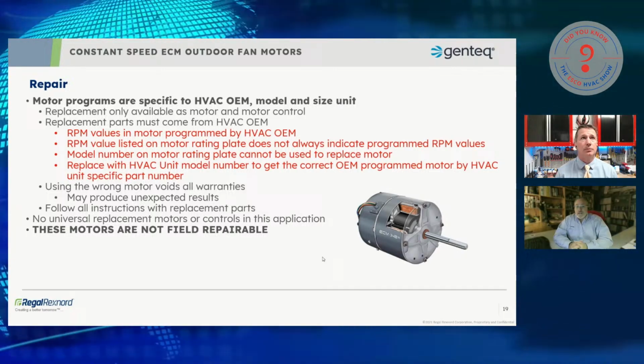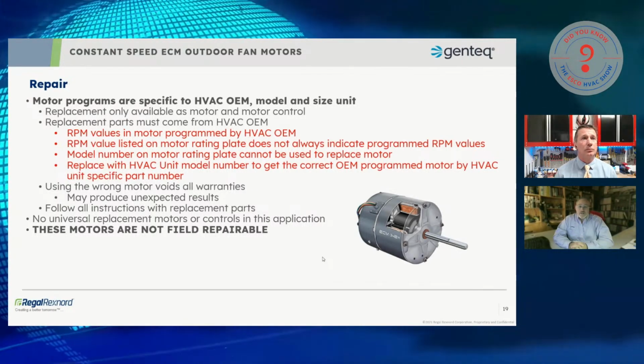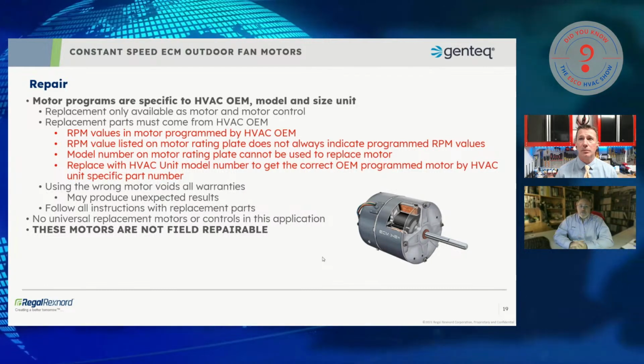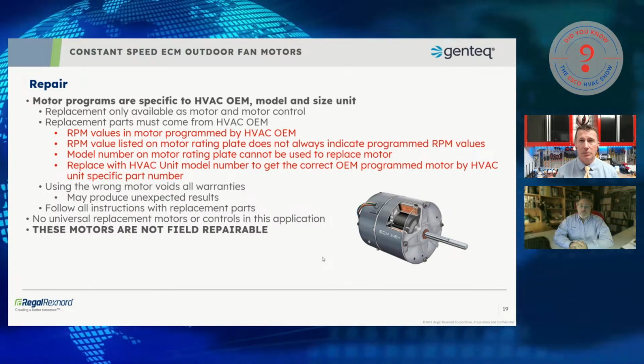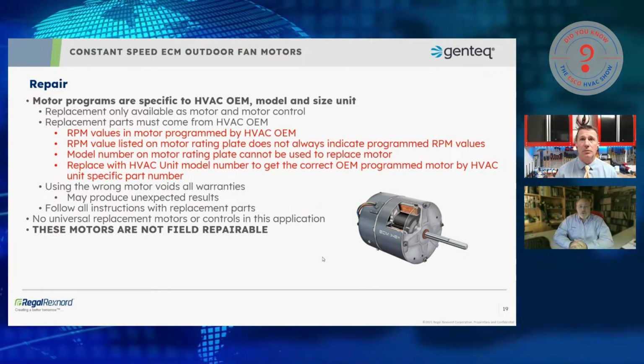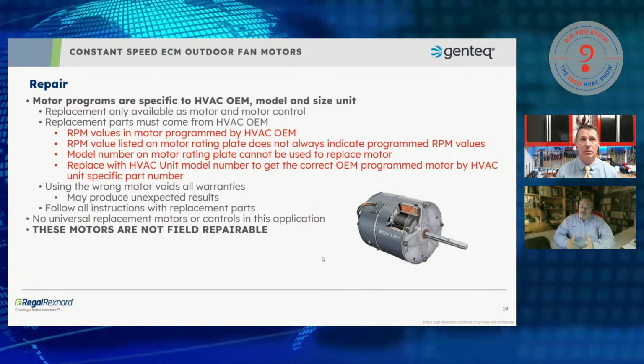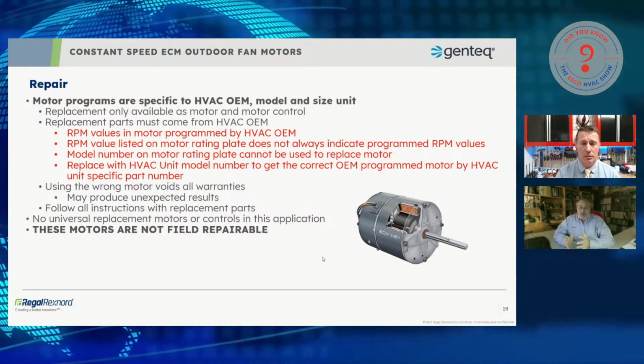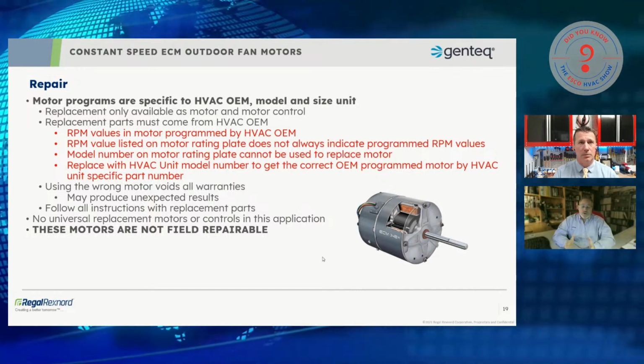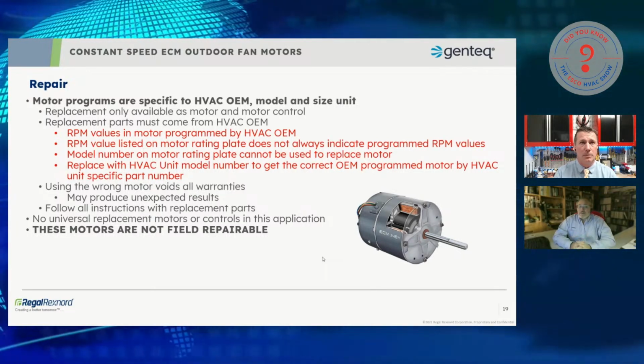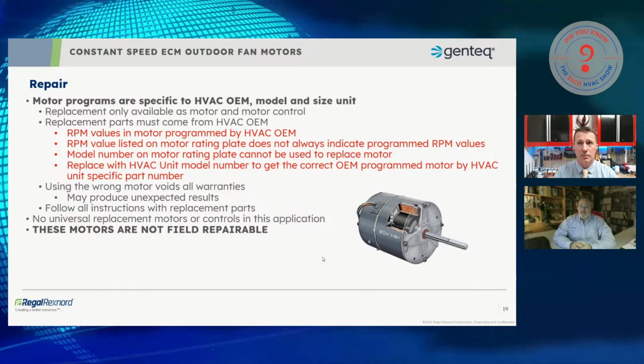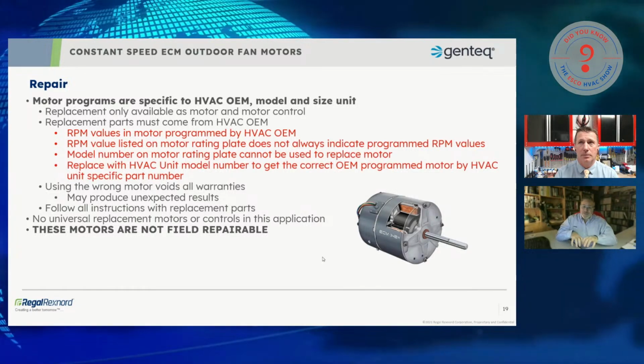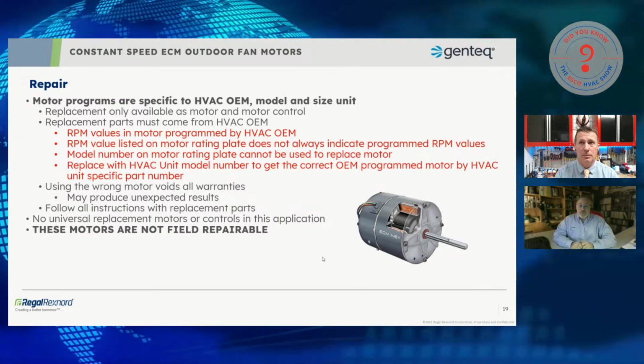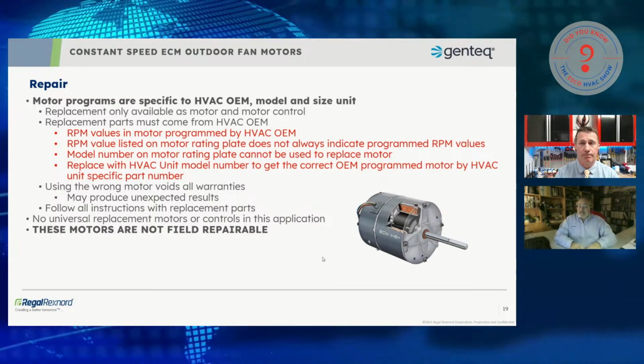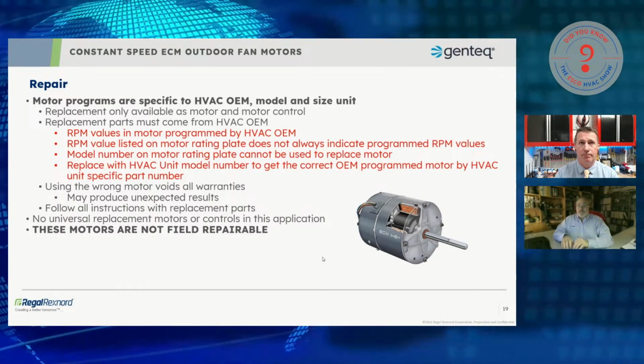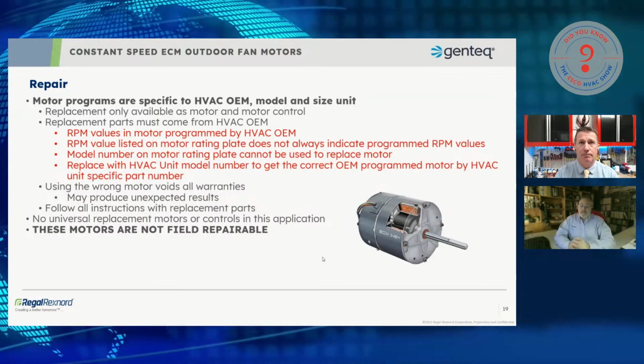So if we do find we have a failed outdoor ECM fan motor, today you do need to go back to the OEM if you want to get exactly what was there. Technicians can do whatever they want to do. They can install a PSC motor. We make some Evergreen outdoor fan motors, but those are designed to replace PSC motors. They're not designed to replace ECM outdoor fan motors. They look exactly alike, but they're not designed today yet to replace ECM outdoor fan motors. They're only designed for replacing PSC.